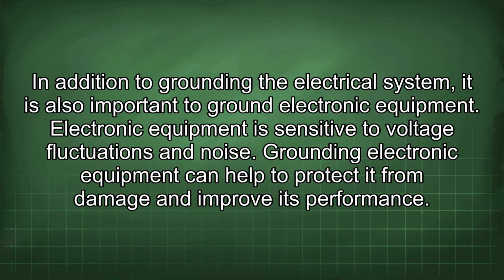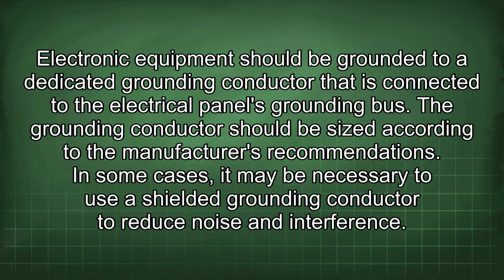In addition to grounding the electrical system, it is also important to ground electronic equipment. Electronic equipment is sensitive to voltage fluctuations and noise. Grounding electronic equipment can help to protect it from damage and improve its performance. Electronic equipment should be grounded to a dedicated grounding conductor that is connected to the electrical panel's grounding bus. The grounding conductor should be sized according to the manufacturer's recommendations. In some cases, it may be necessary to use a shielded grounding conductor to reduce noise and interference.